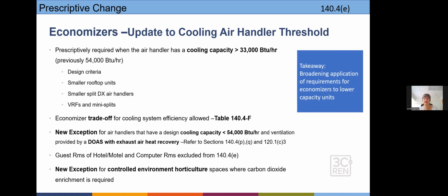The real takeaway here is there's a broadening application of these requirements for economizers, even for lower capacity sized units. That's the new part of the code — it used to be that only very big projects had some of these requirements, but now even our small ones do. A cooling capacity of less than 54,000 BTU/hour, like a residential sized unit, means you're going to see a lot of this come up even for small office projects.